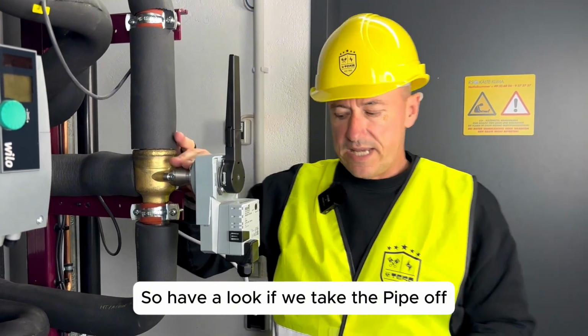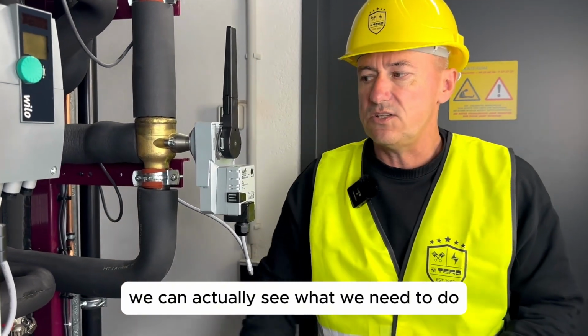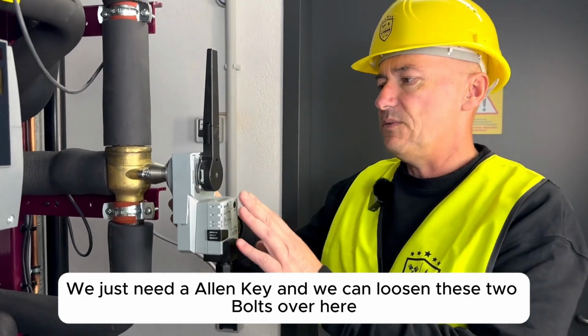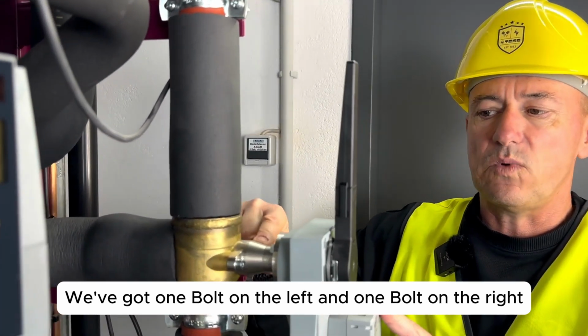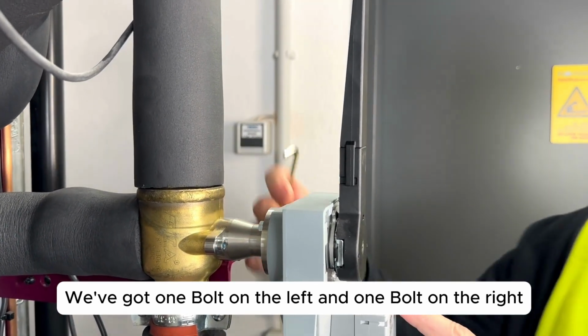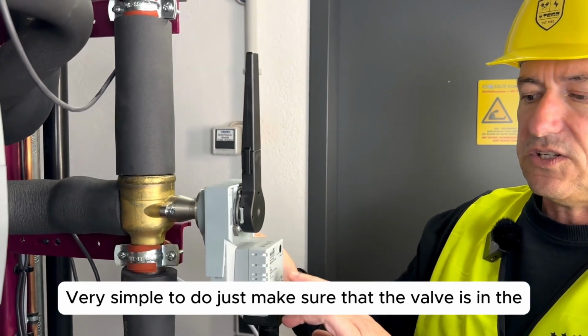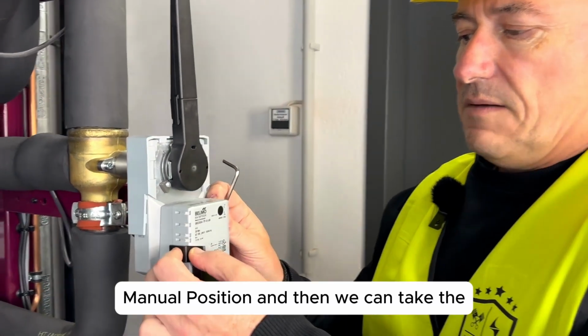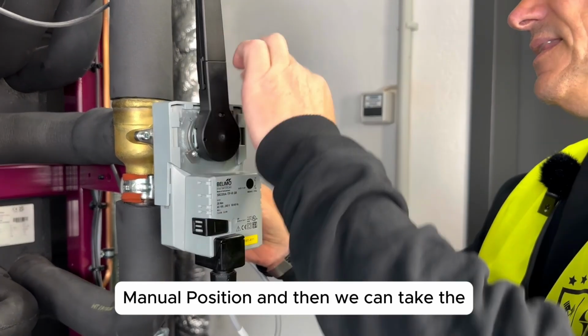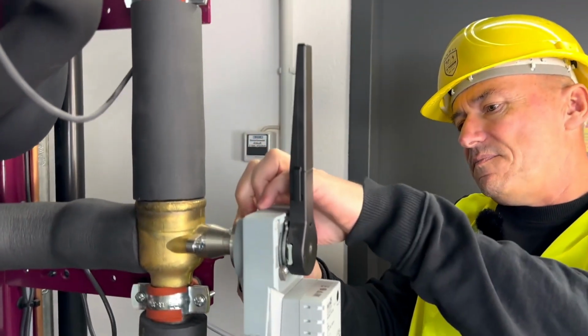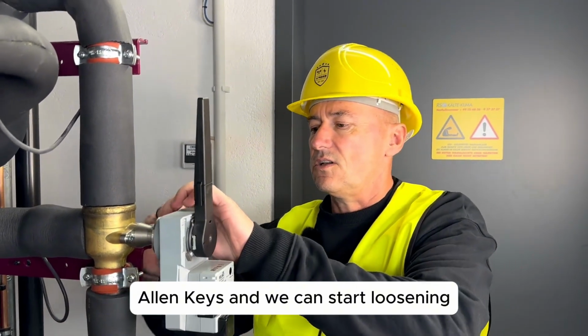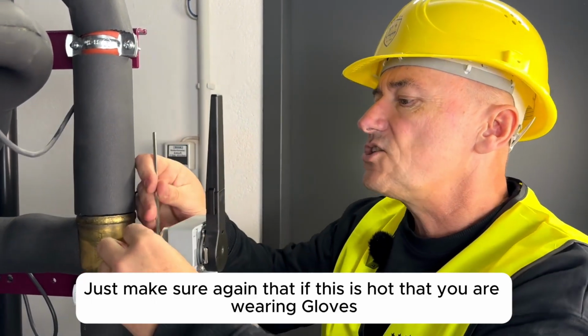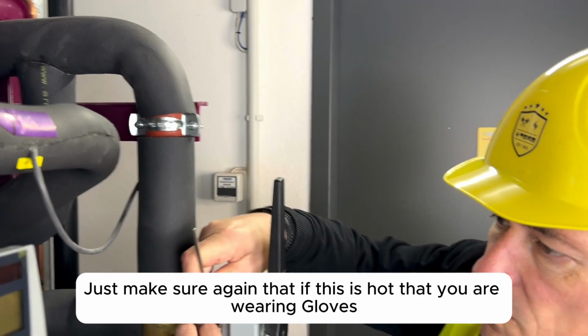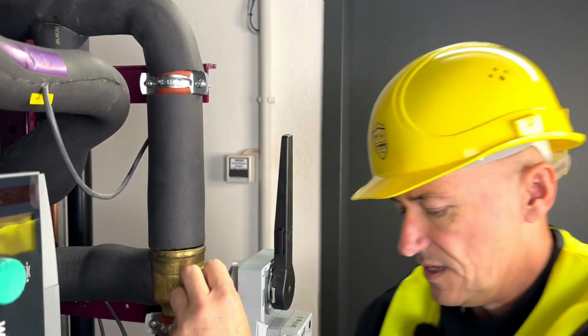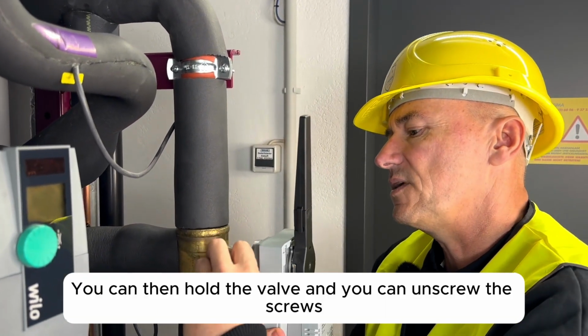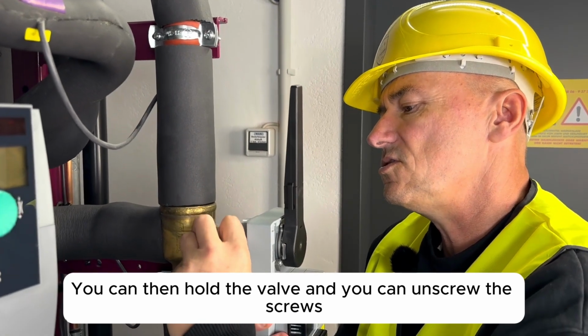So having a look, if we take the pipe off, we can actually see what we need to do. We just need an Allen key and we can loosen these two bolts over here. We've got one bolt on the left and one bolt on the right. Very simple to do, just make sure that the valve is in the manual position, and then we can take the Allen keys and start loosening them. Just make sure again that if this is hot you are wearing gloves. We can then hold the valve and unscrew the screws.